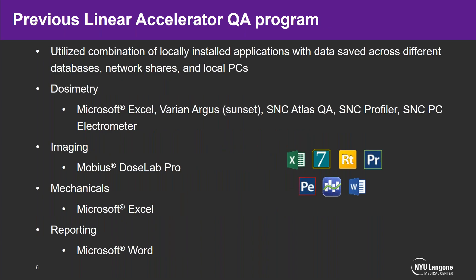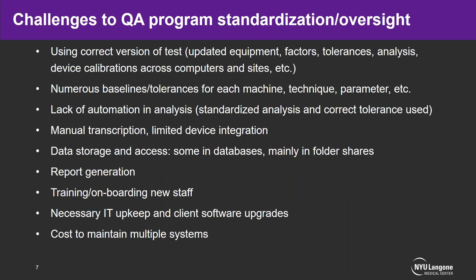Our previous linear accelerator QA program utilized a combination of locally installed applications with data saved over different databases, network shares, and local PCs. We used a wide variety of applications for imaging, dosimetry, and mechanical reporting — just a lot of programs to manage, maintain expertise in, and troubleshoot. The challenges were really standardization and oversight driven: using the correct version of each test, ensuring updated equipment, calibration factors, tolerances, and analysis, and keeping device calibrations consistent across computers and sites.